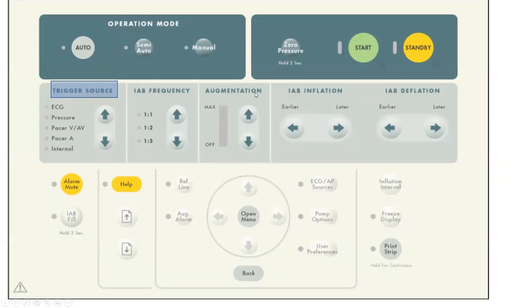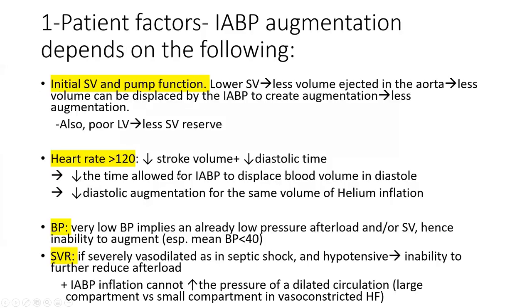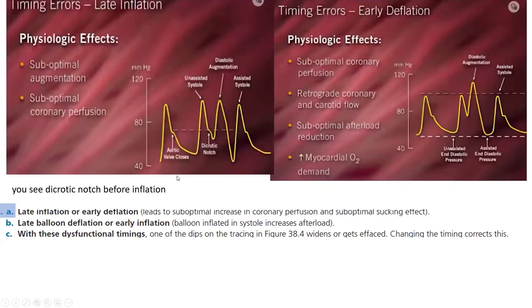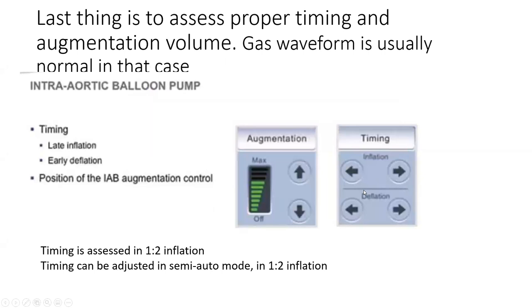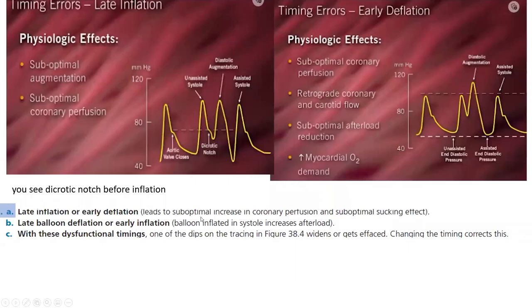So one simple cause for poor augmentation is for some reason somebody played with this, and it's no longer the augmentation on maximum. So you verify it is on maximum. Another thing you verify is the waveform. As I explained, you assess the timing in 1 to 2 inflation under semi-auto mode, and you can adjust the timing. So you see in 1 to 2 mode, are you having late inflation in a way that you see the dicrotic notch, or are you having early deflation? So late inflation or early deflation will lead to suboptimal augmentation, suboptimal increase in coronary perfusion, and suboptimal sucking effect.